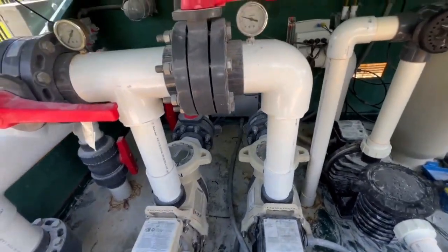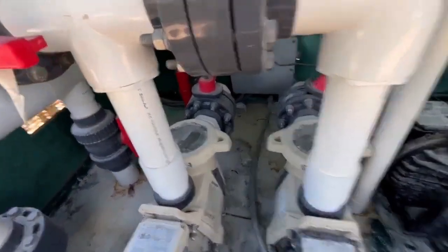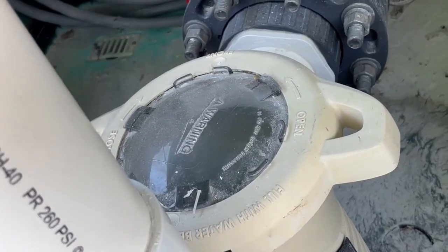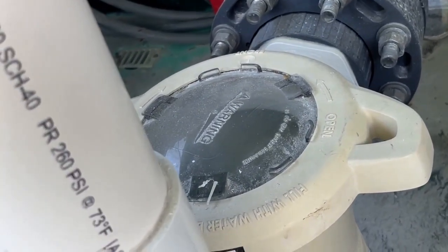These motors are working well, okay? How do we know? There's barely any bubbles on the top. That's how you can tell, okay? If this was low, if there were a ton of bubbles at the top, we know we have a problem. We know we have a leak somewhere, and that affects the performance of the pool, and it will burn out the motor. This is a well-run machine. There are no leaks. Also, if the filters are dirty, you'll see a ton of bubbles at the top because it's just sucking more air.